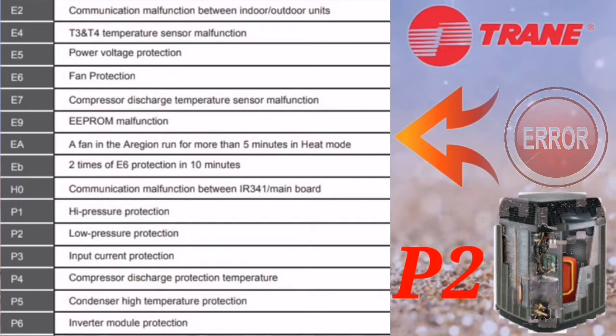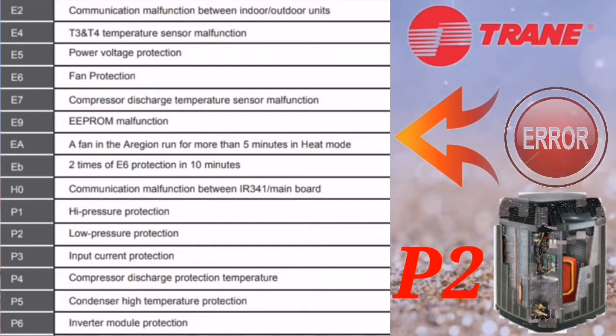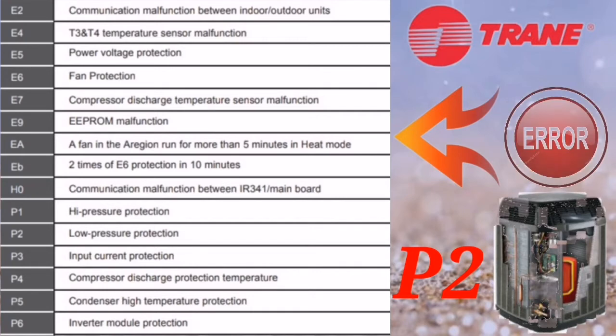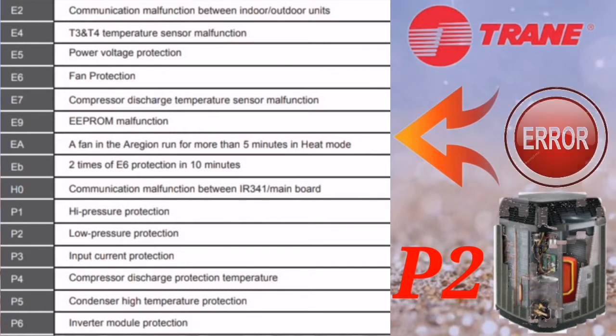The next error code is P2, which means low pressure protection, also called LP switch protection. This occurs when there is a lack of refrigerant in the system. Charge the refrigerant according to the back pressure specification. If the LP switch is broken and not sensing properly, replace the LP switch. If the outdoor PCB is not reading the pressure correctly, replace the outdoor PCB.